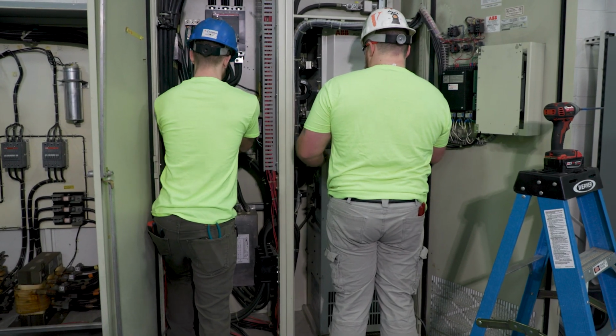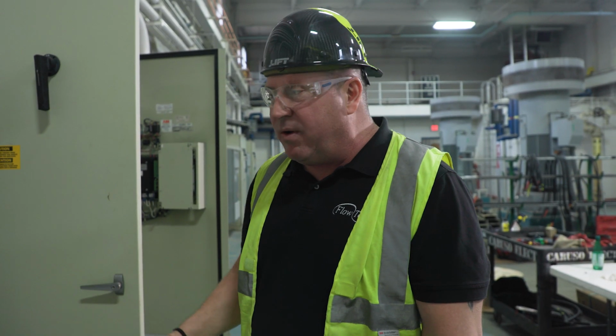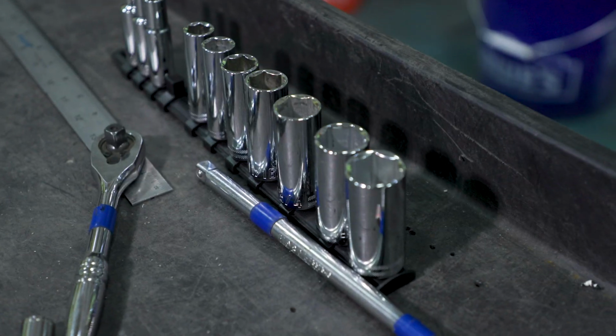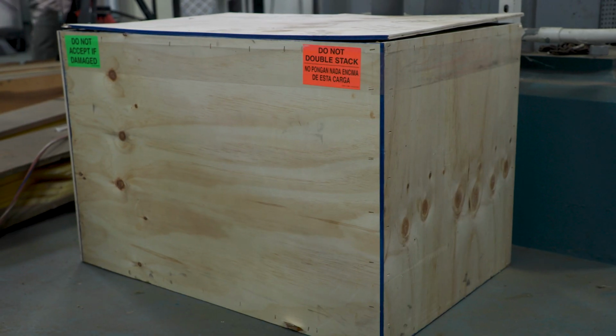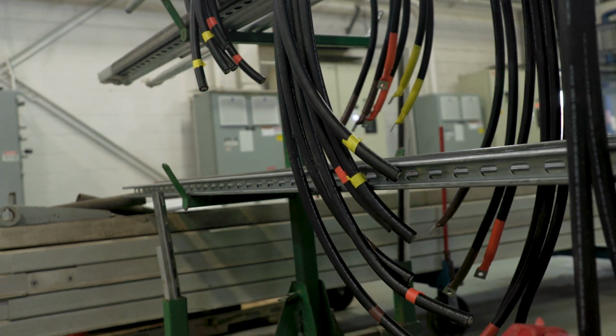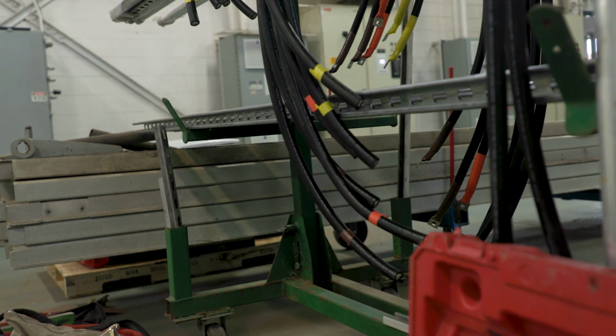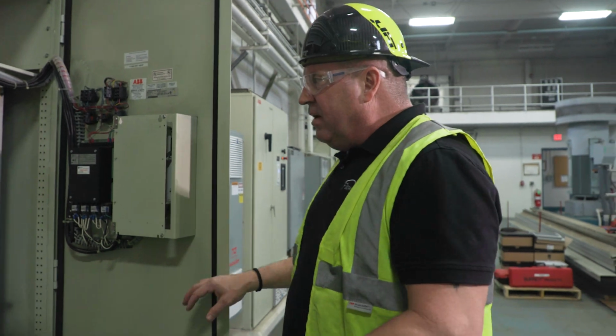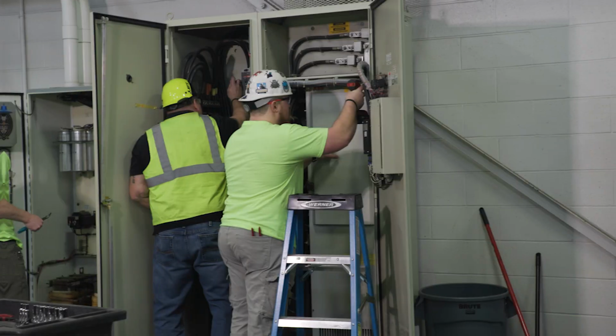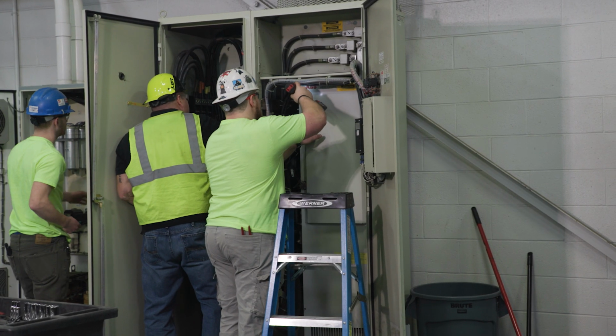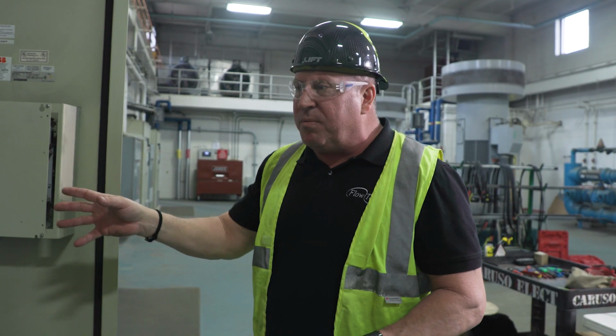A lot of it's pulling out. That's usually the first day we're pulling out. And then we start putting it back together. Our filter is in the box there. Pre-cut some cables that are hanging up over there for the wiring of the VFD. When we're ready and the drive's out, I'll get in here and I'll mount the mounting panel. So easy removal of the new VFD once we put it in.